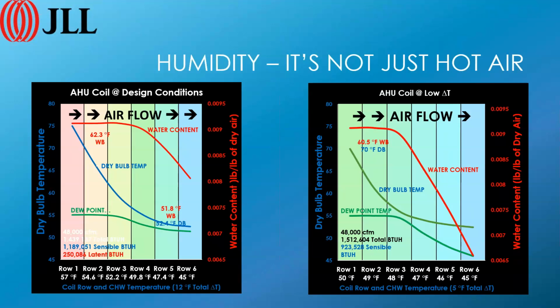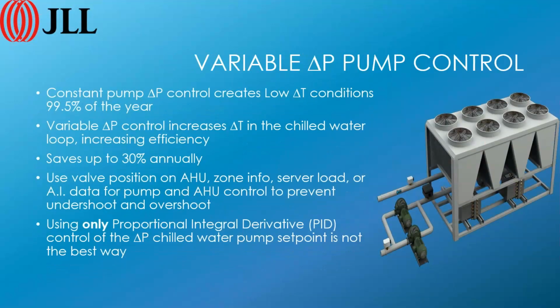So even though this is a sort of reduced load, the delta T is lower, you're actually pulling more water out of there, and the total BTUs, there's 100,000 BTUs more that you're pulling out of that coil at a lower delta T. So just running at a lower delta T just wastes energy by dehumidifying more than you need to. So what we want to do is find a way to vary delta P throughout the year, and we change that delta P in response to things that are going on inside the loop. And this is one of the things we're going to talk about in a little bit more detail today.